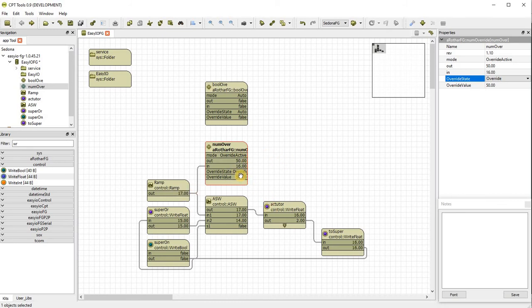So we usually grab these 2 values here. We put them into the supervisor. In Niagara is what we typically use. You would put a status demux. You would override this value here. This comes in as a numeric writable. You override this value. You put this through a status demux. It gives you an output on override. You put that into the state. Again, it's a bit messy, but this is Sedona, people. Work with it. So, yeah, I mean, it's a cleaner way of doing it, really.